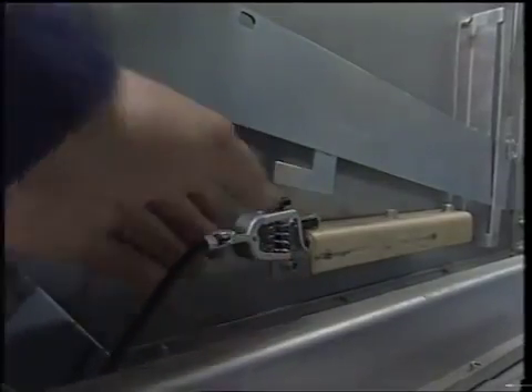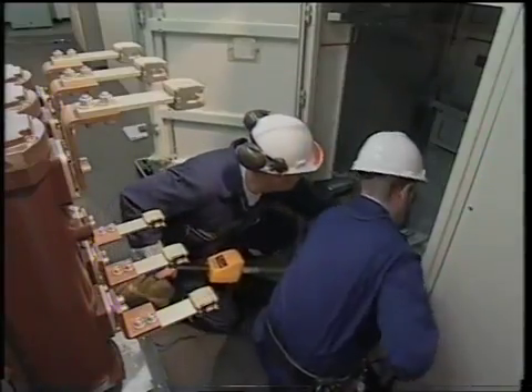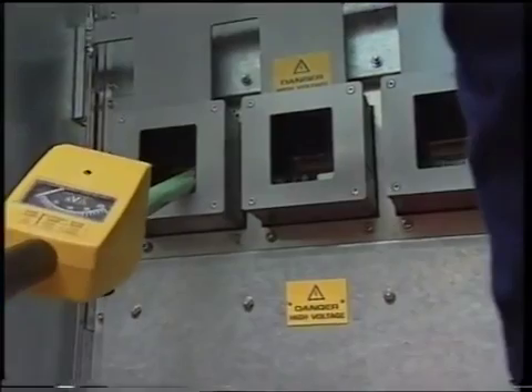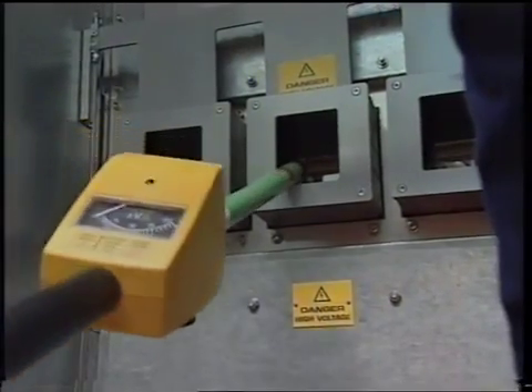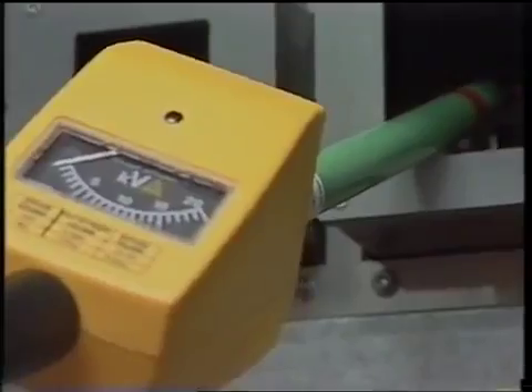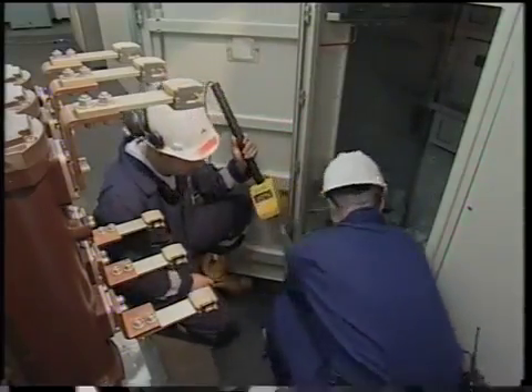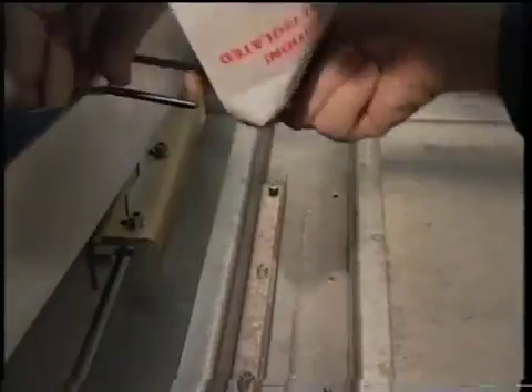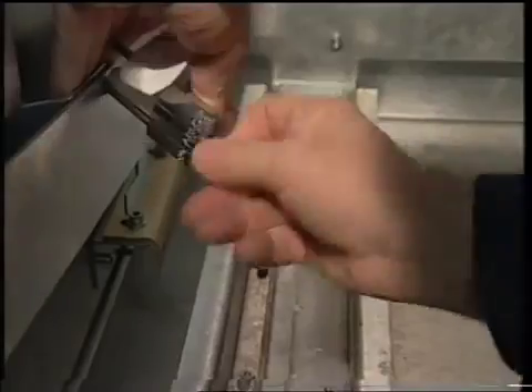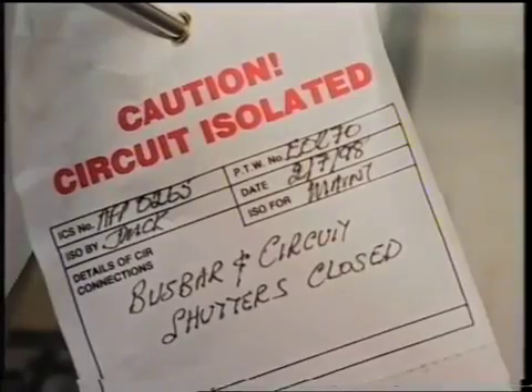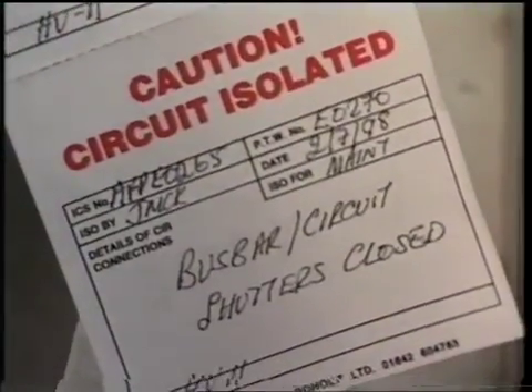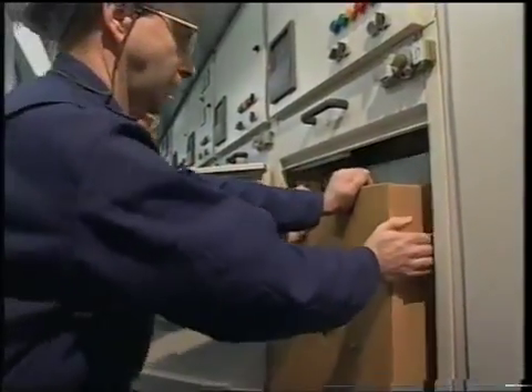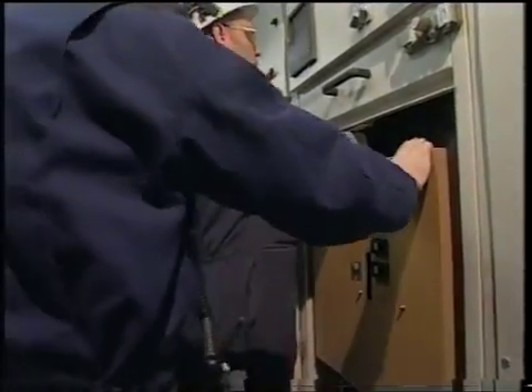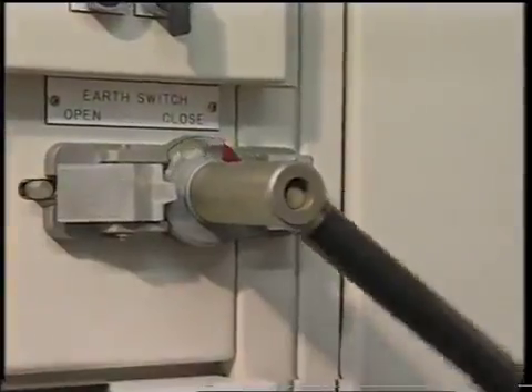The prod's earth lead is connected to a point in the cubicle, and the individual phases of the circuit are tested with the prod and confirmed dead. Don't forget that the prod must be rechecked for correct operation after the test has been performed. When satisfied that the circuit is dead, the cubicle shutters are locked off and the CETO attaches a label confirming it is isolated, the bottom half of which is torn off and attached to the permit to work. The circuit breaker is pushed back into its enclosure to guard against any ship movements. The circuit earth switch is now closed onto the outgoing circuit.